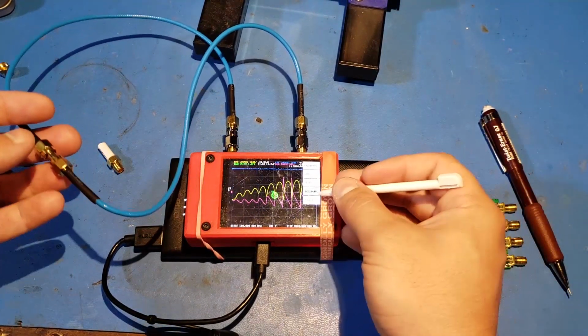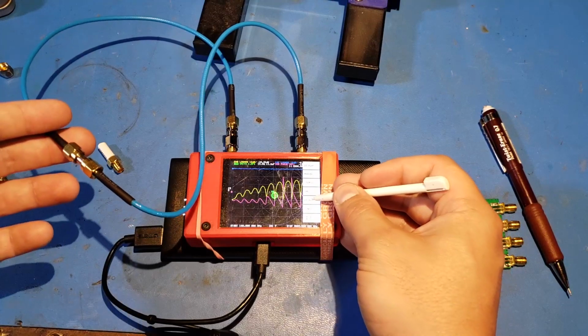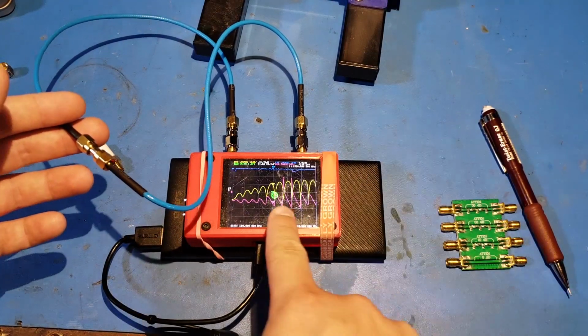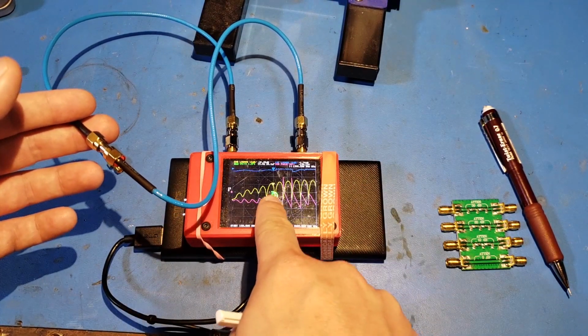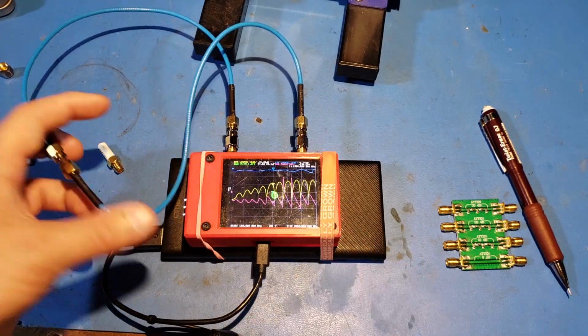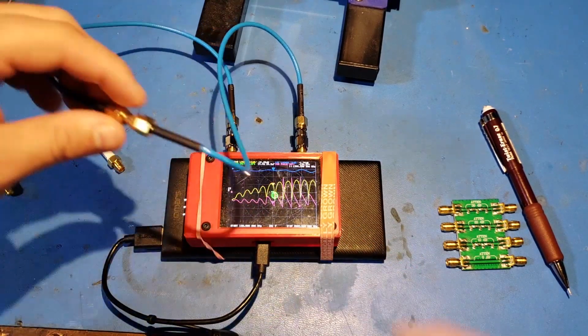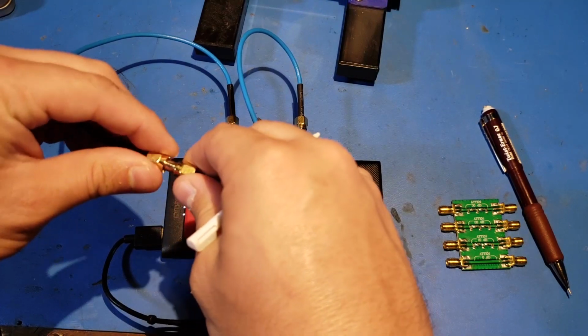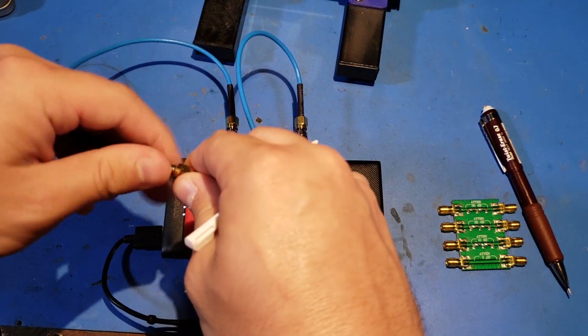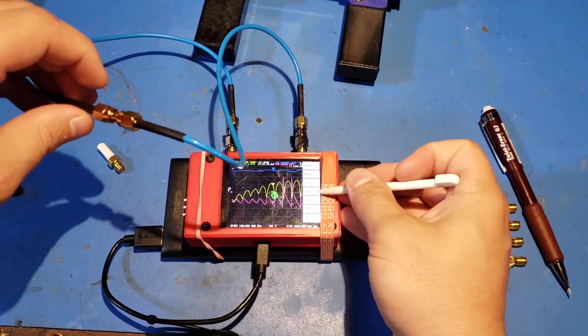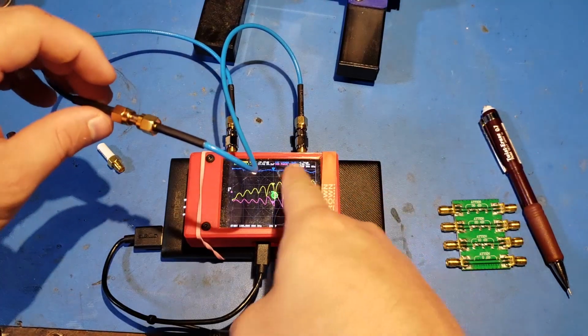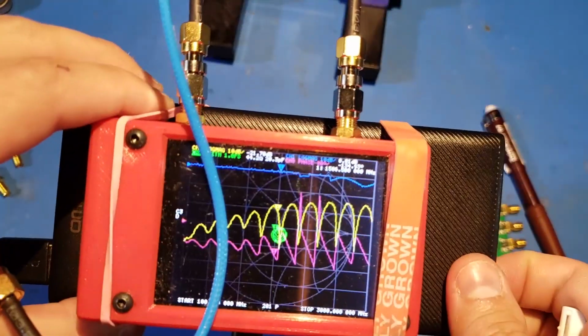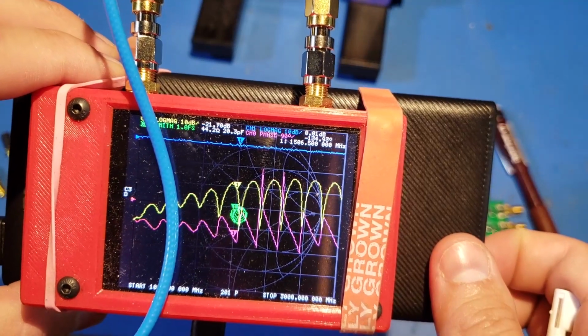So now if we go and we recall Save 2, that should look different because we haven't actually calibrated it, and we can see that our through measurement falls off from unity and now has a couple dB of attenuation, which wasn't there when we actually had the valid calibration applied. So we know that those two are indeed different. Here, if I recall 3, it should go up on the through measurement to having basically no attenuation, 0.01 dB, so that's unity.